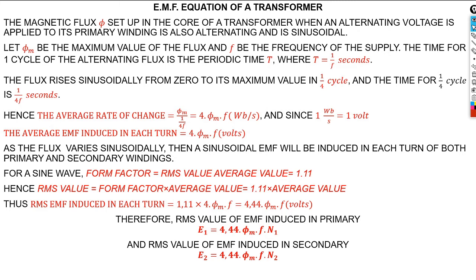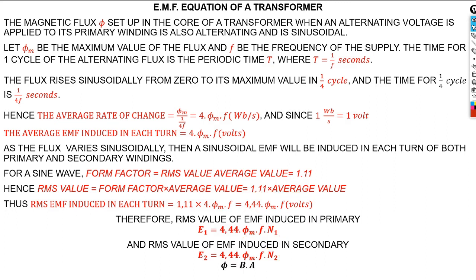The RMS value of the induced EMF in the primary is given by that equation, where we now include the number of turns. This is for one turn, but as the number of turns increases, the voltage increases significantly. The same equation applies to both sides of the transformer — primary and secondary — just using the respective number of turns N1 and N2. The flux is the same for both. Also remember from Electrical 1 that flux equals flux density B times the cross-sectional area A of the ferromagnetic core. The three important formulas to note are these.